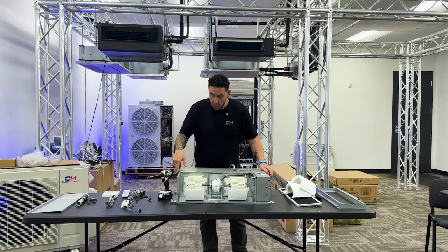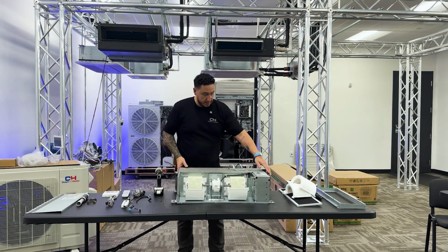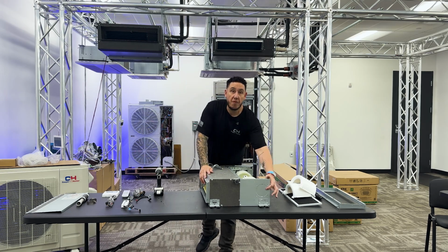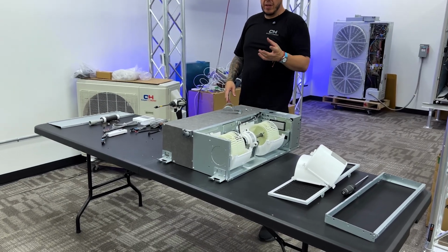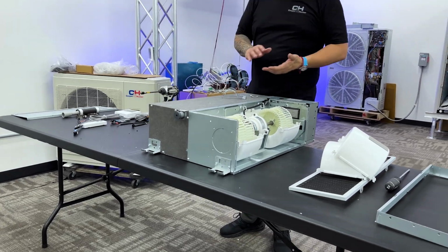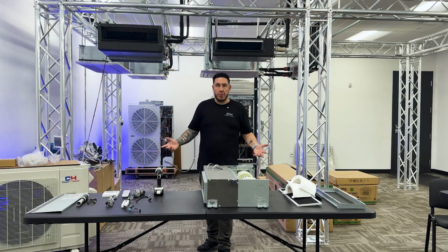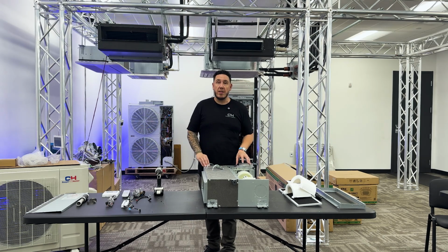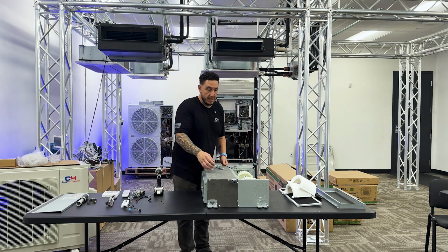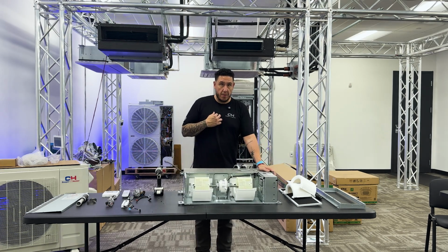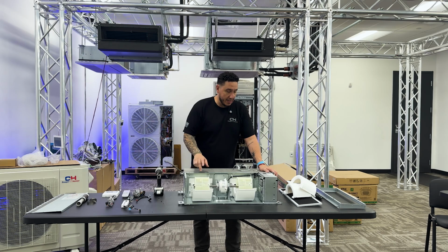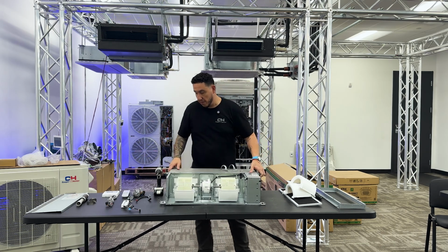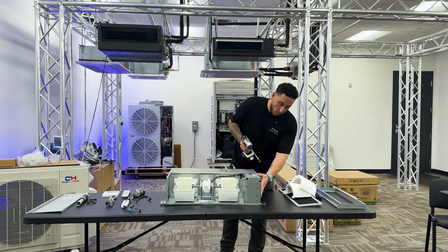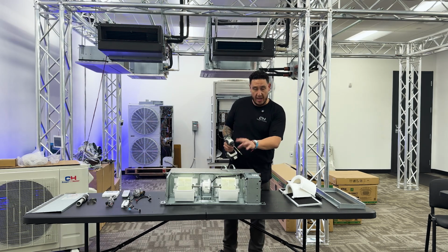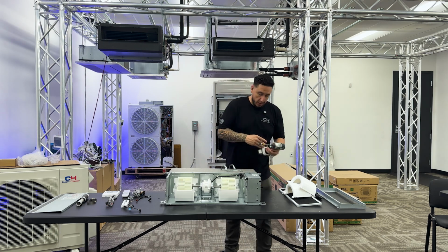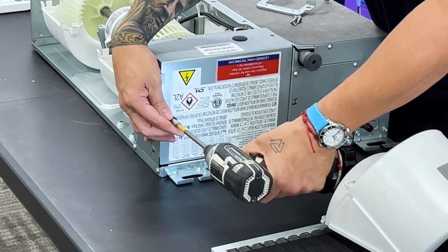Now, we do have a fresh air knockout built into this system, just like we do with our 4-way cassette. So we could add ductwork to this unit, install a third-party inline fan if it's required per code. Now we could supply fresh air to this unit and it'll disperse it in the application that it's installed. Again, we don't make a third-party inline fan, but we do provide a connection point on our board, 230 volt connection, where the technician could wire directly up to this unit and power that fan every time this unit calls for cooling. It'll activate the fan, and every time it shuts off, it'll deactivate the fan.